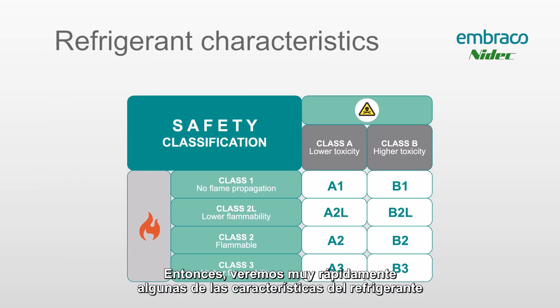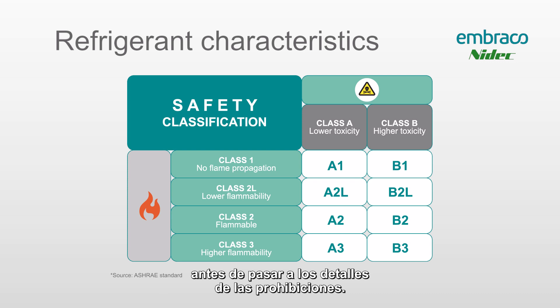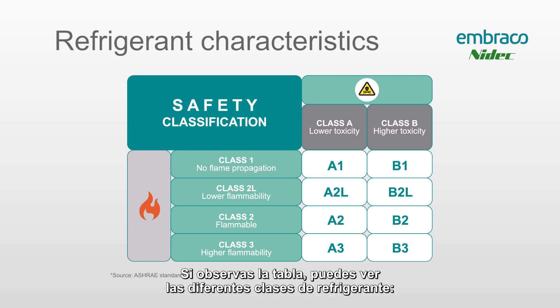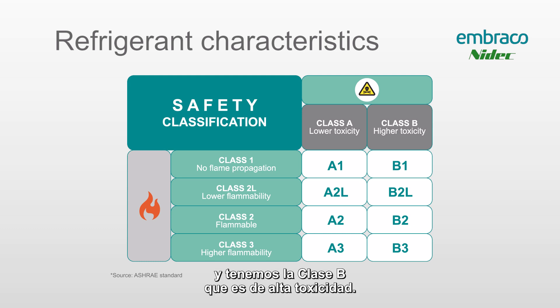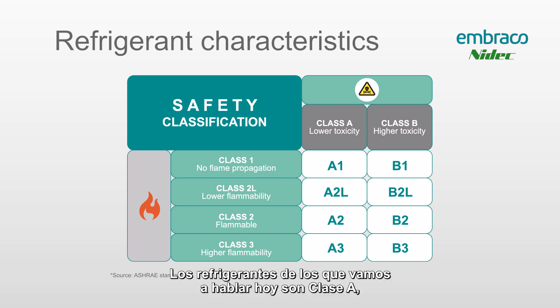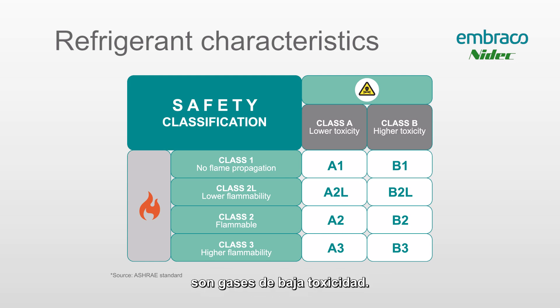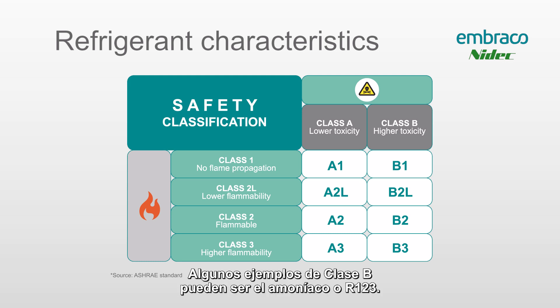We'll look at some refrigerant characteristics before we jump into the specifics of the bans. If you look at the chart, you can see the different classes of refrigerant — Class A and Class B. Class A is low toxicity and Class B is high toxicity. The refrigerants we'll be talking about today are Class A — they are low toxicity gases. Some Class B examples might be ammonia or R123.